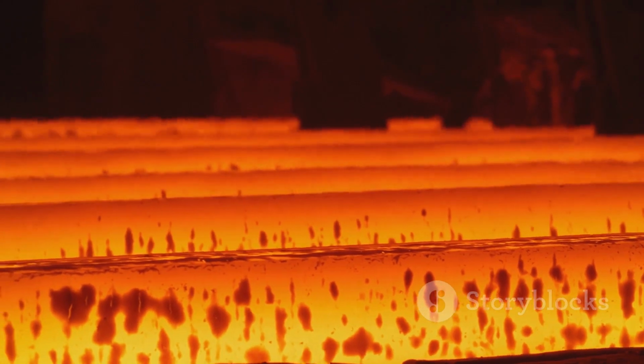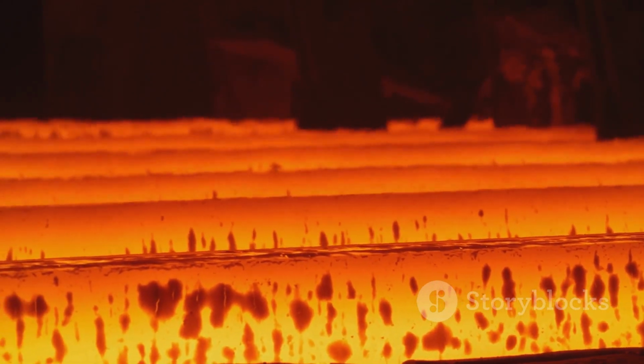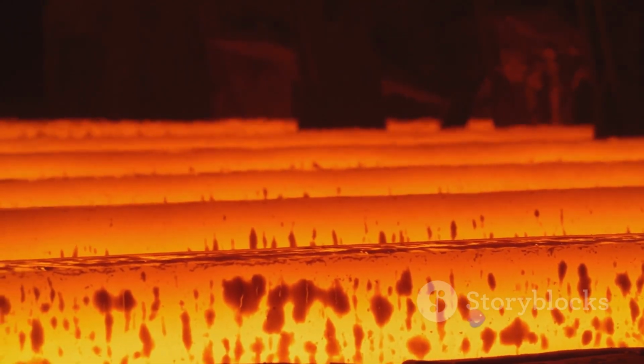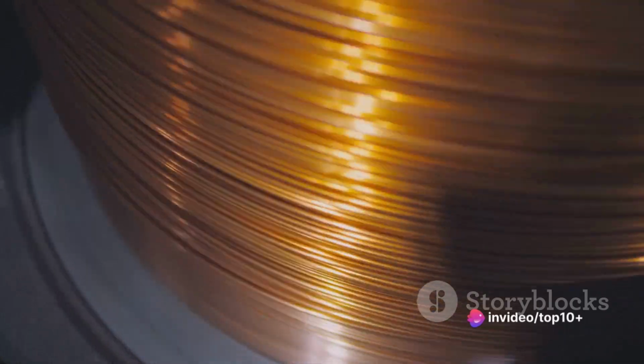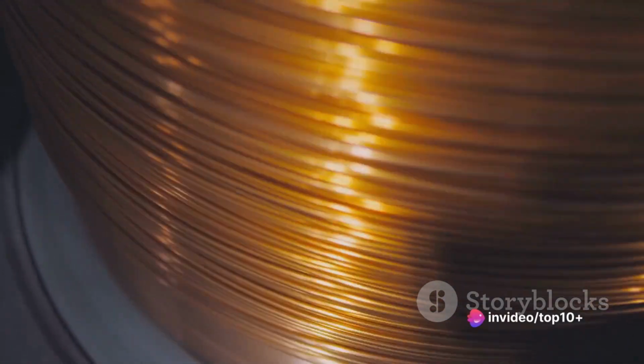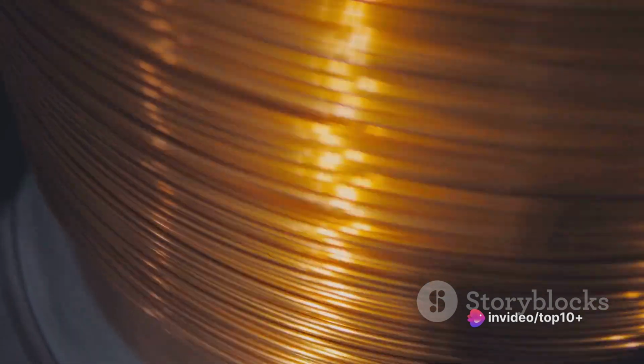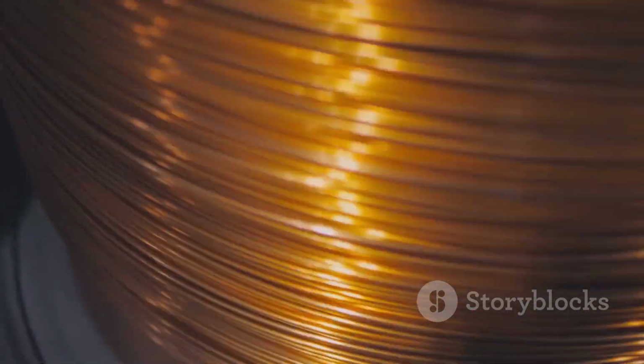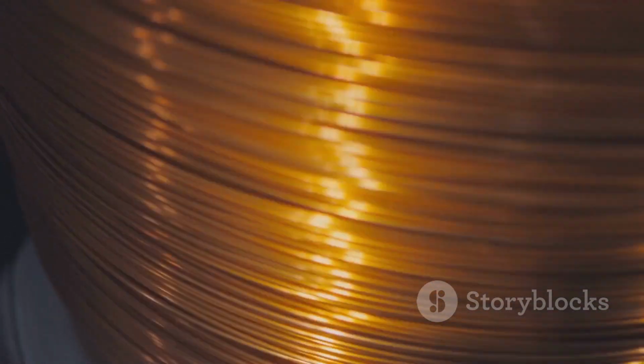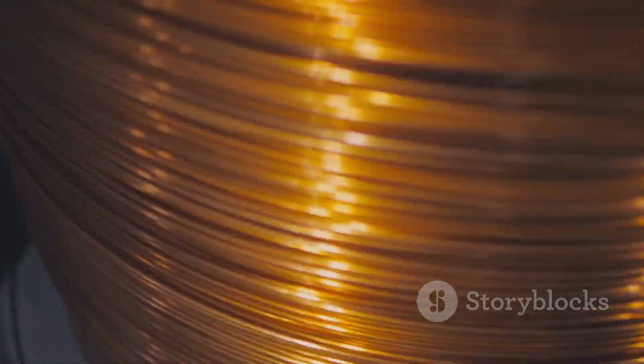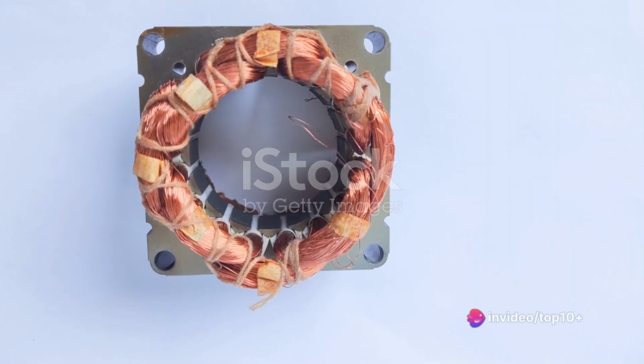The first step is detection. An MCB is essentially a guard, constantly monitoring the electrical current flowing through a circuit. It's equipped with a bimetallic strip and an electromagnetic coil. The bimetallic strip is sensitive to heat, which is generated by current. Meanwhile, the electromagnetic coil reacts to sudden surges in current.